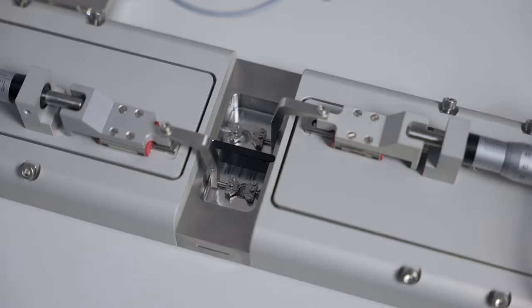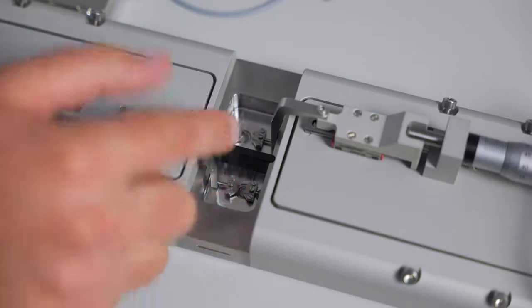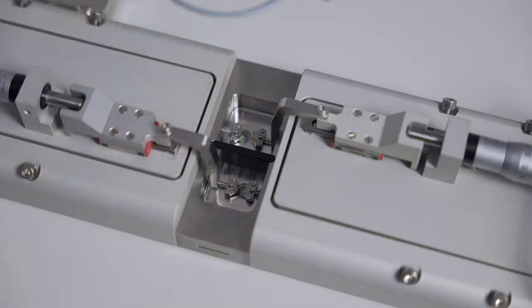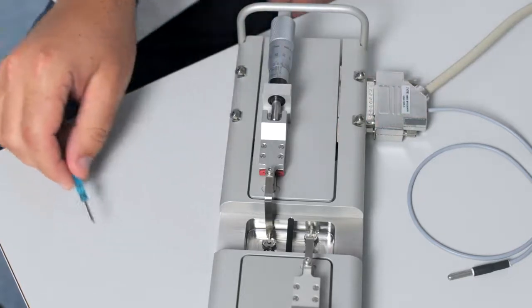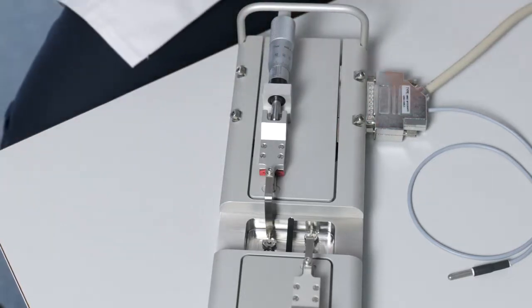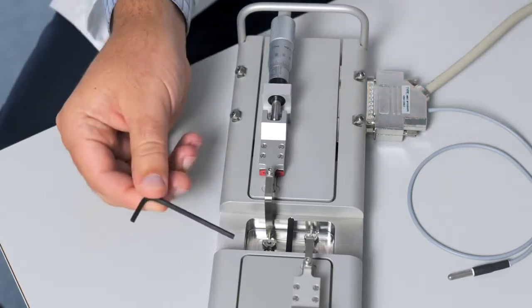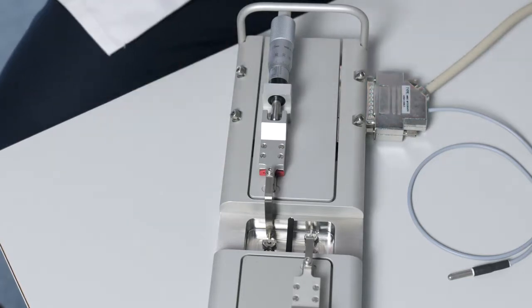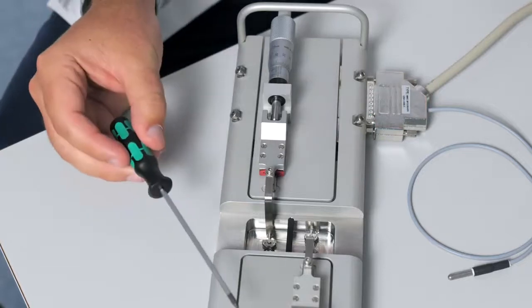Anytime you are working in the chamber, you need to be very cautious with the force transducer side, as this is a very sensitive piece of equipment that is collecting the small forces from your isolated tissue. To get the most accurate data from your experiments, you will want to make sure that your two sides are perfectly aligned. You will need the small screwdriver, the larger of the two Allen keys that came with your system, and the ball-end screwdriver.